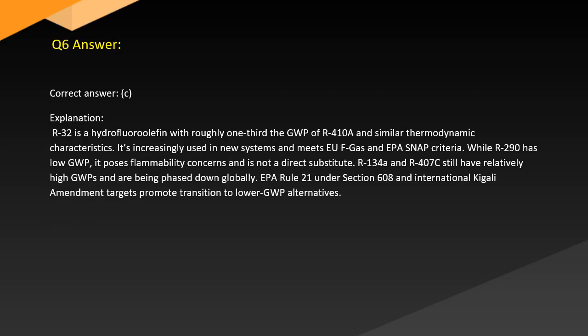Answer. Correct answer: C. Explanation. R-32 is a hydrofluorocarbon with roughly one-third the GWP of R-410A and similar thermodynamic characteristics. It's increasingly used in new systems and meets F-gas and EPA SNAP criteria. While R-290 is an option, it poses flammability concerns and is not a direct substitute. R-134a and R-407C still have relatively high GWP and are being phased down globally. The EPA Rule under Section 608 and the international Kigali Amendment targets promote transition to low-GWP alternatives.